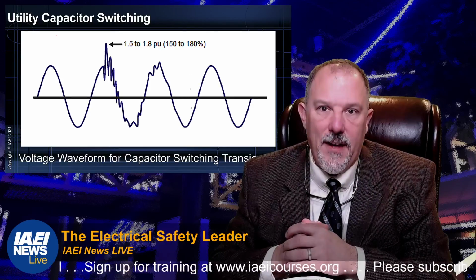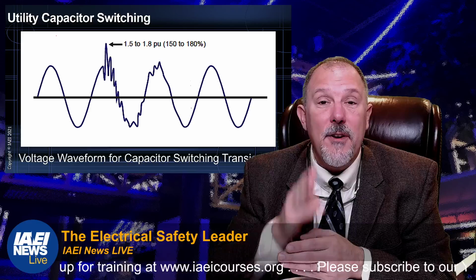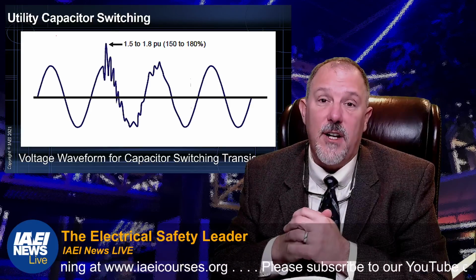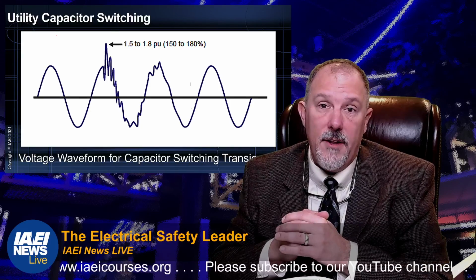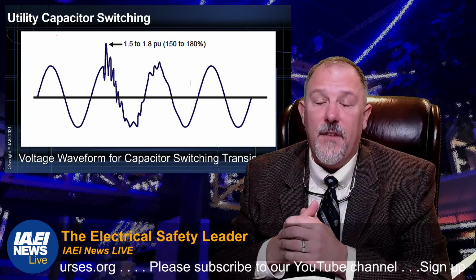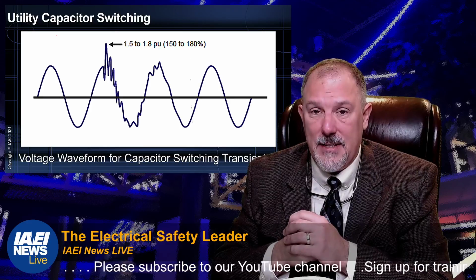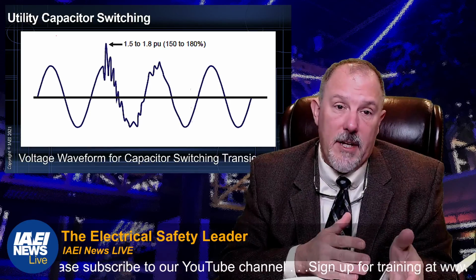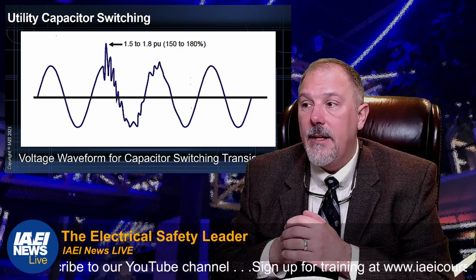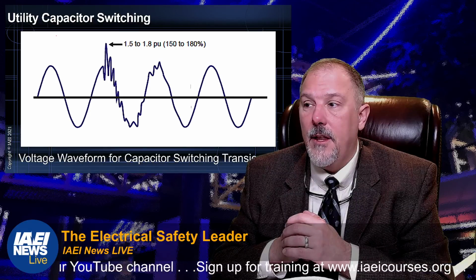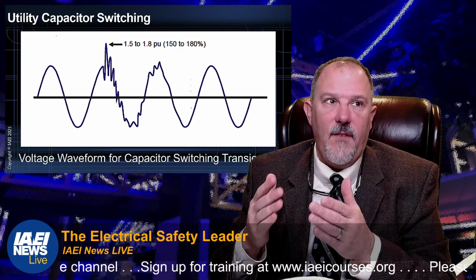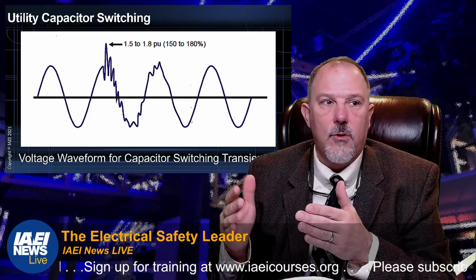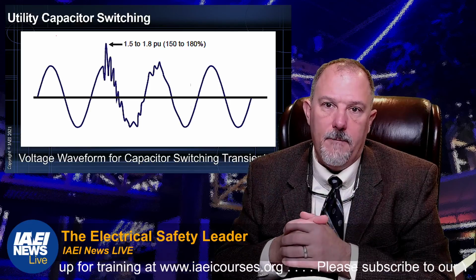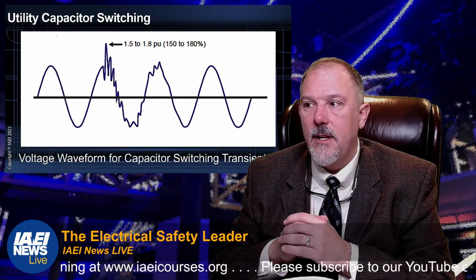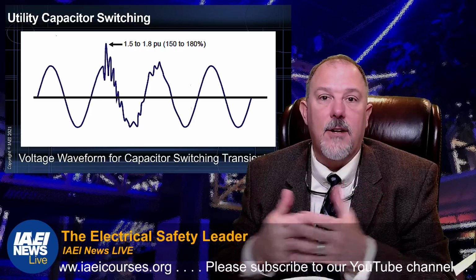that transient event was causing enough current. We had 30 milliamp ground fault protection of equipment on those early branch feeder AFCI devices. These are the branch feeder, not the combination types. And this was, I believe, even before the National Electrical Code formally adopted AFCIs. It was just in our test units.